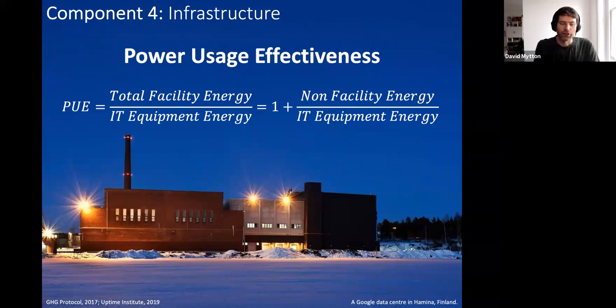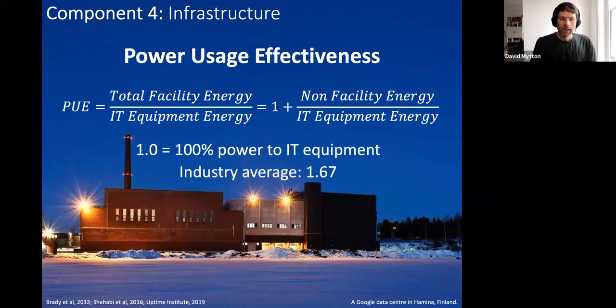The industry uses a common metric called power usage effectiveness, or PUE. This is a ratio between power drawn by the infrastructure components and the power delivered to the servers, disks, and networking equipment. The ideal value is 1.0, meaning 100% of the power going into the data center goes to the IT equipment.